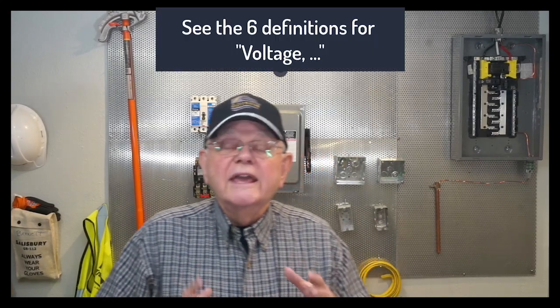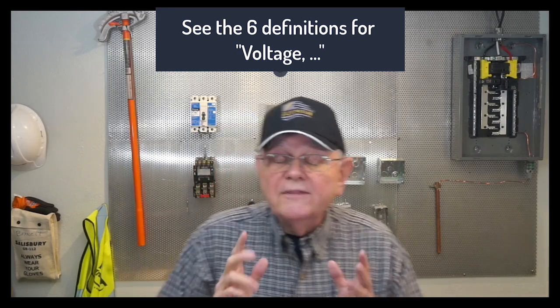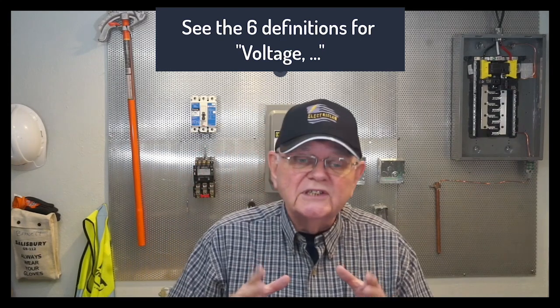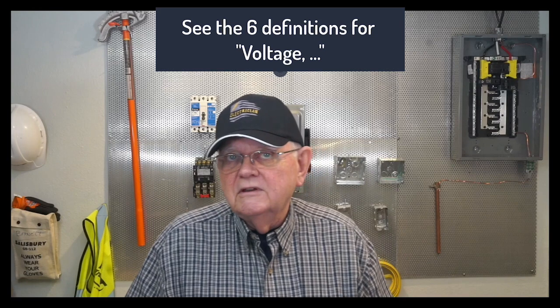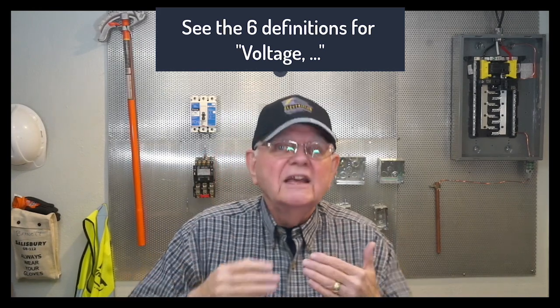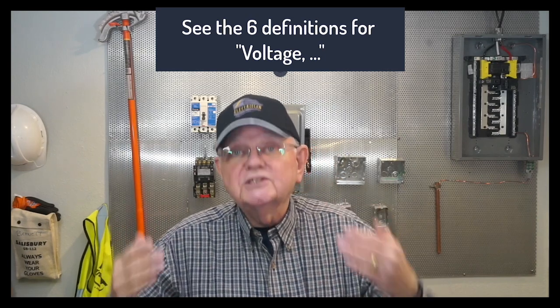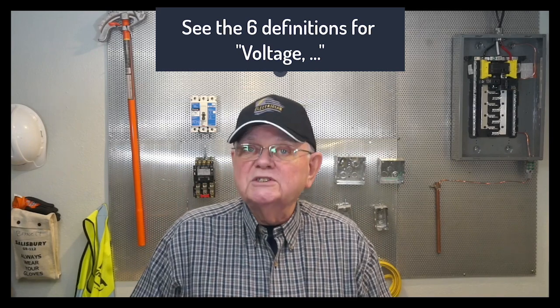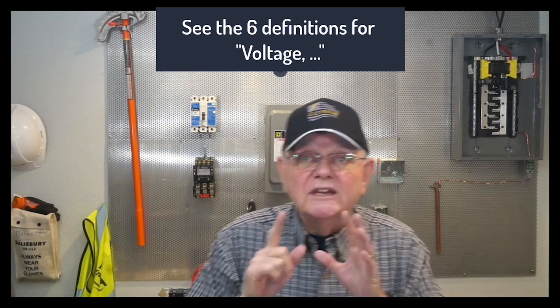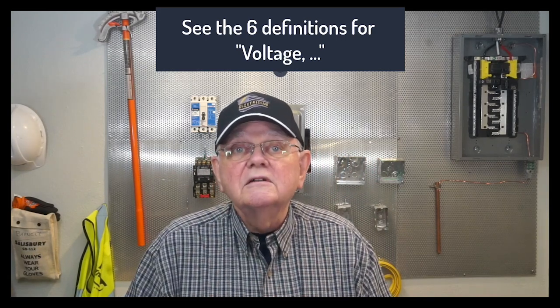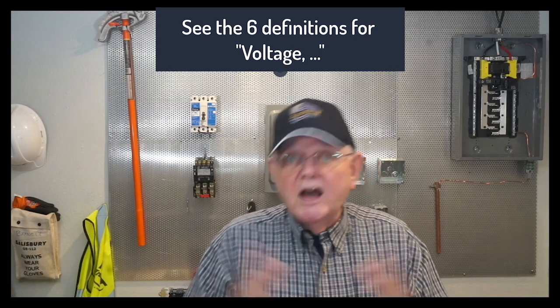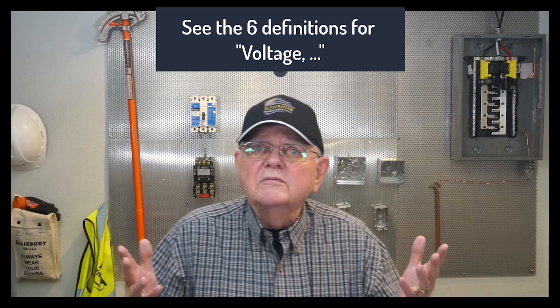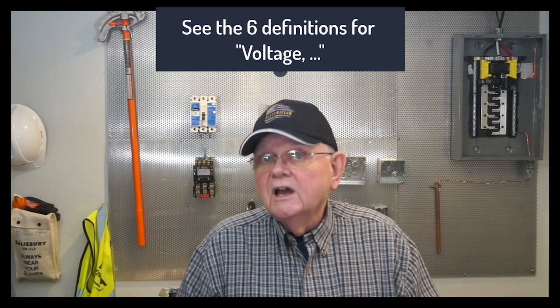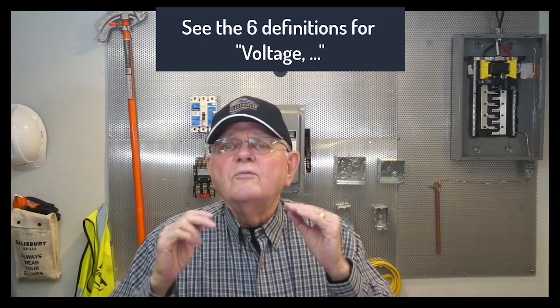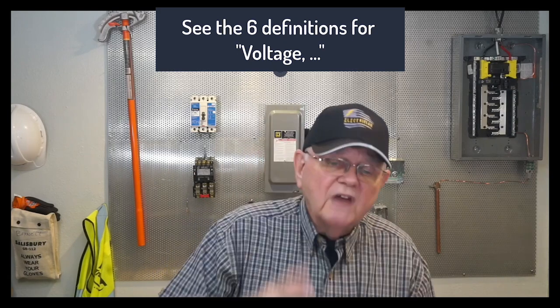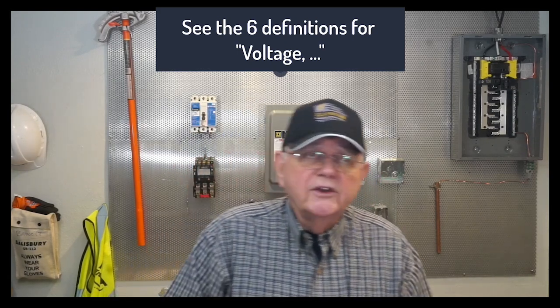Another thing I want to clear up is voltage levels in the NEC. And I think where people get confused on the different voltage levels is they try and read things into the NEC. The National Electrical Code does not specify the different voltage levels for our systems and equipment. It's pretty specific on what it specifies as voltage levels. There are 6 different definitions regarding voltages in the NEC. And some of them we're familiar with, right? Like the nominal system voltage, the voltage assigned to the system. We do have a definition for high voltage. High voltage, it says it's the potential difference of more than 1,000 volts nominal. Say, oh, okay, that's high voltage. And you say, no, that's not, that's medium voltage. And on it goes, right?